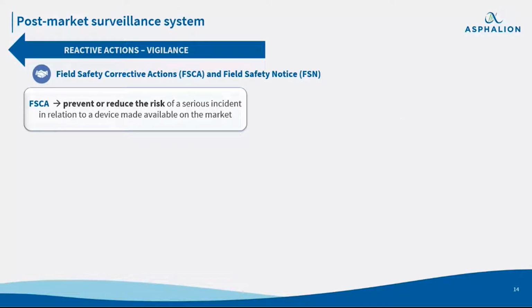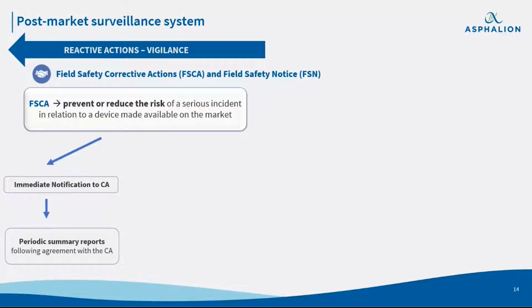Another very important concept related to vigilance and incident is the field safety corrective action. The field safety corrective action means corrective actions taken by a manufacturer for technical or medical reasons to prevent or reduce the risk of a serious incident in relation to the IVD available on the market. When we are in a situation of a field safety corrective action, an immediate report to authorities is required even before the FSCA being undertaken. In addition, the manufacturer may provide periodic summary report following agreement with the competent authorities.